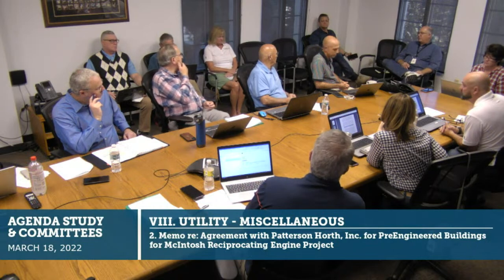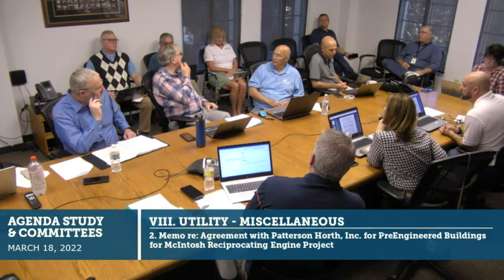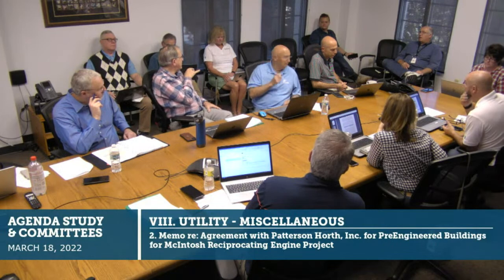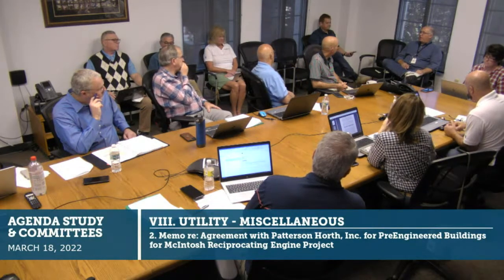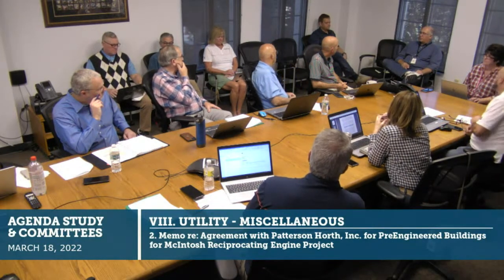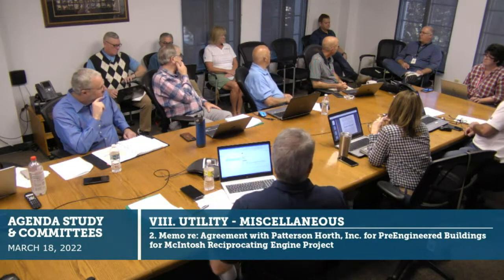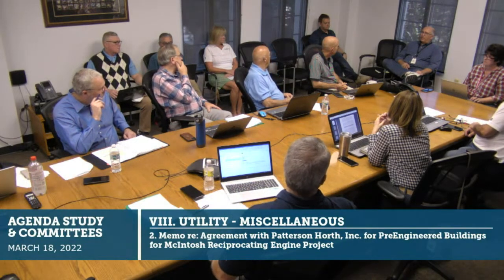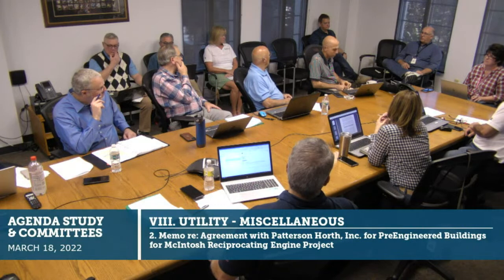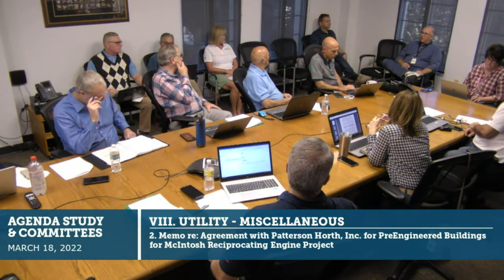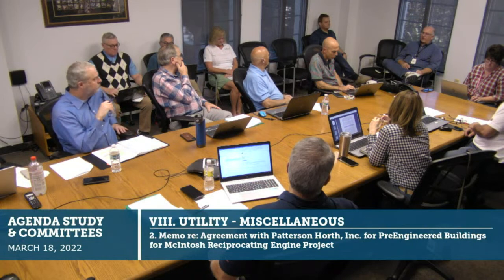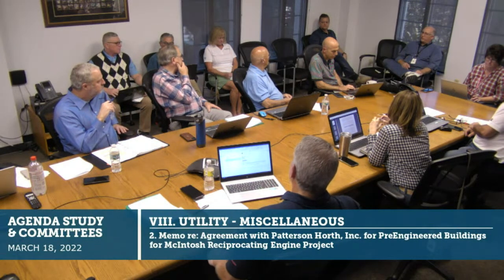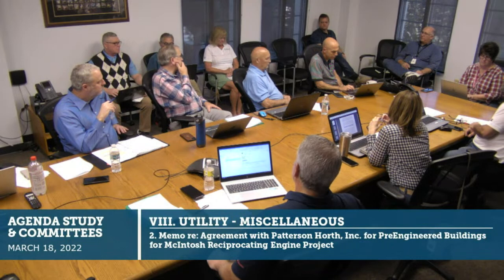So the batteries in the ancillary building, are those for starting the units? Those are for backup power for the control systems, to make sure an electrical blip doesn't cause an issue. And even though we aren't building these units to be a NERC-certified Black Start unit, these units will have the ability to Black Start. That's one of the things we planned for here.